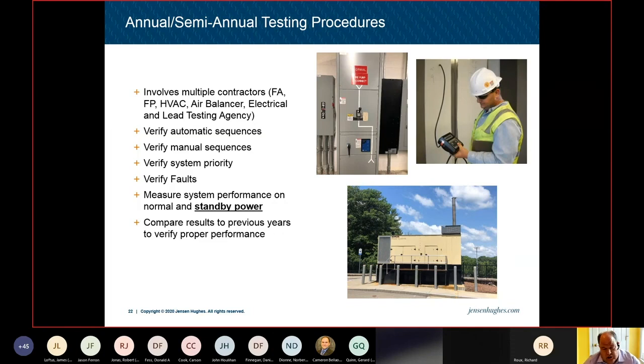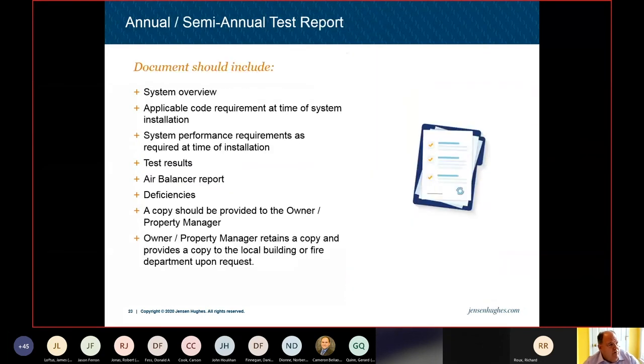Now, if there's not proper performance, just like any other inspection, testing, and maintenance procedure, deficiencies and corrections are written up and provided to the owner, who is then responsible for getting those items corrected. That could be various things. It could be electrical, sprinkler, fire alarm, or HVAC. It could be any number of things that had a problem. Most of them are HVAC related, especially when you're going through it for the first time. There's a lot of issues there.